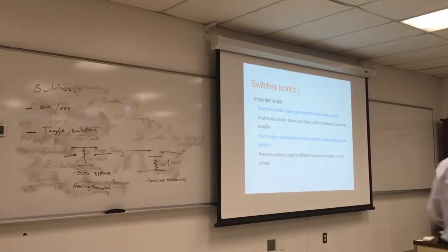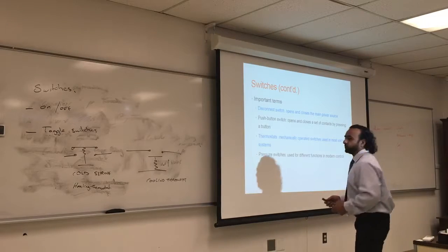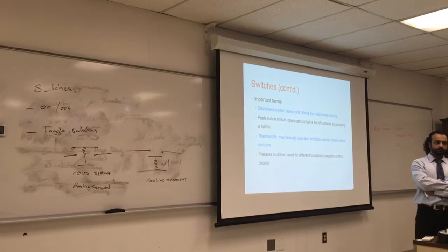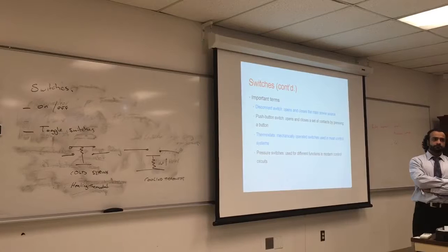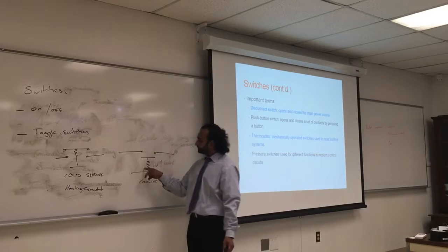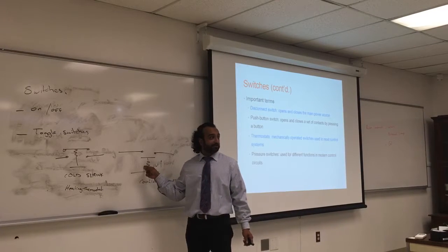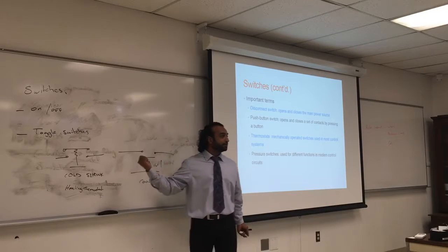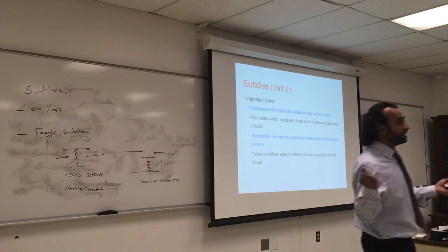We also use mechanical ones. Question for you. I know in one of our homeworks for one of Bill's classes, it said something about you couldn't adjust the heating delay, or the differential. Is that why? Because you mechanically can't move it that far? That's one of the reasons, yeah. This is a spring. The spring K factor, or the expansion rate, is calculated and already preset. So it's the way it is. You have to change the entire spring.